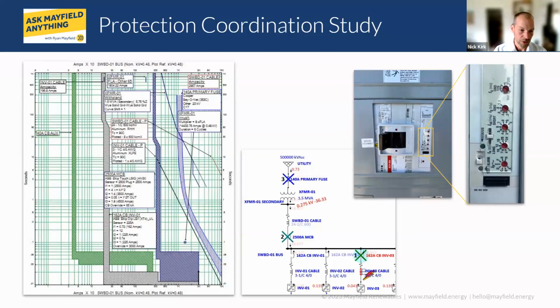And then the picture to the upper right is showing that for a main circuit breaker, a lot of times we have several dials to set on the main circuit breaker. In this case, we have instantaneous, long and short time trip, and ground fault. And so these settings that we get from ETAP would then translate into how we program the device in the field.